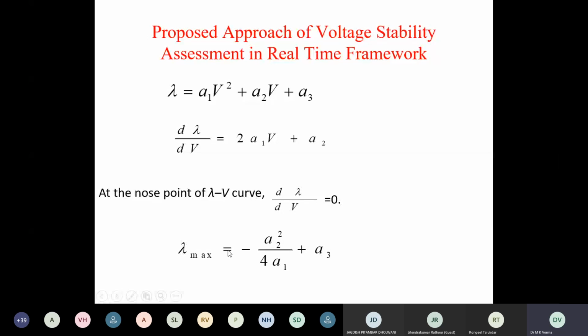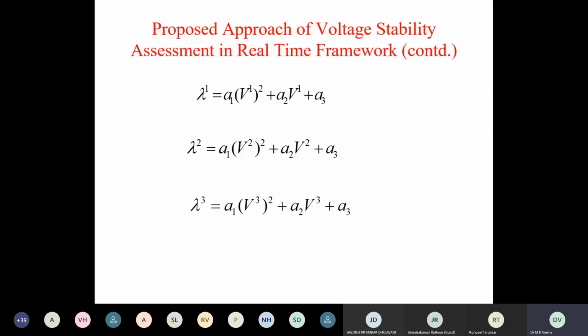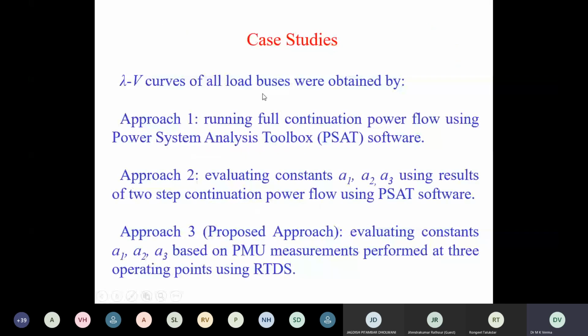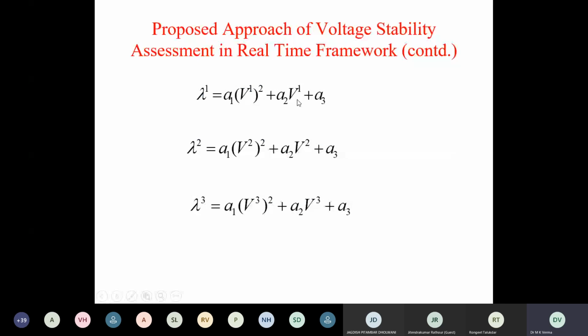So these constants he has evaluated using 3 PMU measurements. Now, suppose this is a loading factor at some of the load for which measured voltage was V1. Then the equation is valid for that point. Lambda 1 can be given by A1 V1 square plus A2 V1 plus A3. Similarly, for other loading points, say this is lambda 2, measured voltage is V2. And third loading point, lambda 3, measured voltage V3.